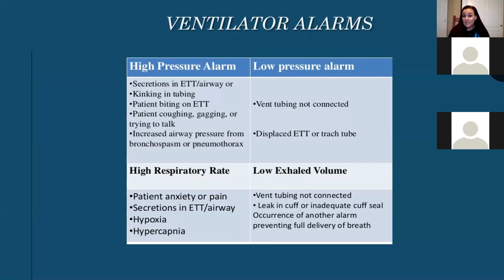I like the low exhaled tidal volume alarm, especially when I'm in a pressure control mode, because if I get busy in the helicopter and I'm mixing drips and making my phone call into the ER, when that starts to go off, you know that compliance is starting to go down, and you get a real quick indicator that this is where you need to start messing with these things.